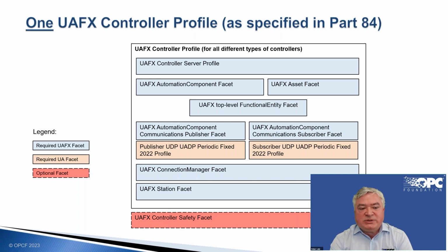And in this overview, you see all the required facets out of UAFX. This is in the light blue. And out of UA specifications, this is the light orange here. And the only optional facet that we defined in this profile is the safety facet, because not all controllers are supporting functional safety and fail-safe communication. So this is good news because it provides a common foundation for really cross-company and cross-application connectivity horizontally between controllers.